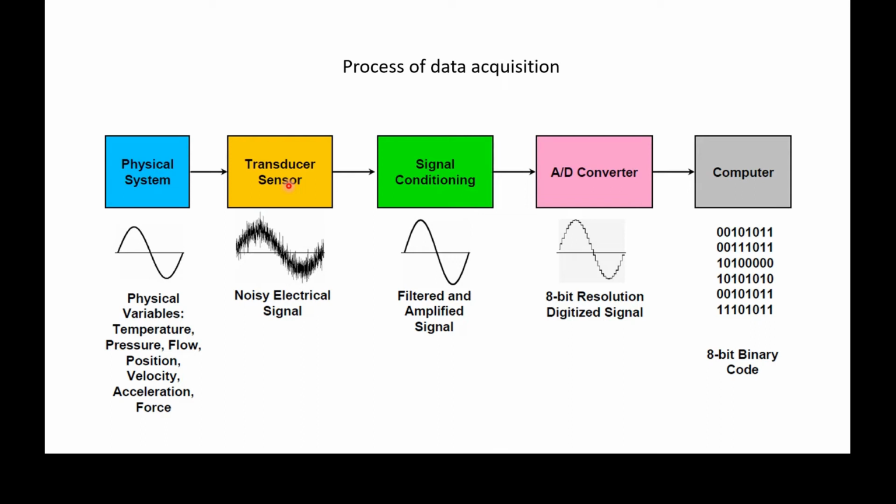You simply used your ruler to measure what the trace was doing in terms of how big it was and how fast it was and so forth. Well, we have progressed many, many years beyond that to the system that we use these days that's pictured here, where we transduce everything from its physical change into an electrical change.